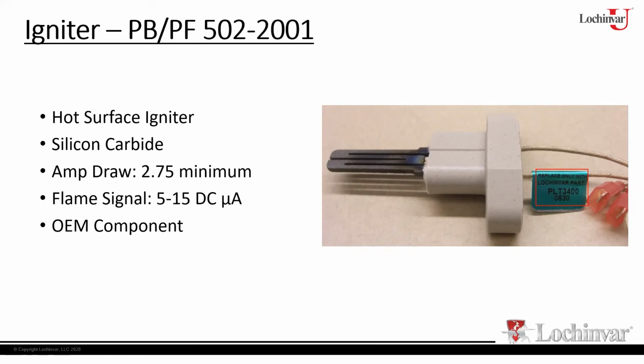Now, for some reason, say the amperage goes up to 2.75 amps and the timer starts, but then it drops below that. Well, at that point, the timer will stop. And then it's going to say, hey, we're not drawing the proper amperage. We're going to go into a lockout. It's going to say lockout HSI low, typically is what you would see there. All right. So we want to make sure that the igniter is drawing the proper amperage.